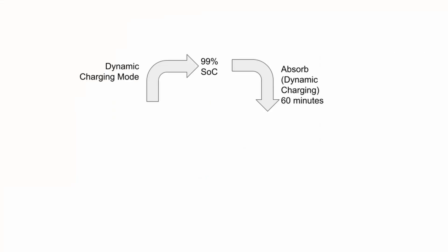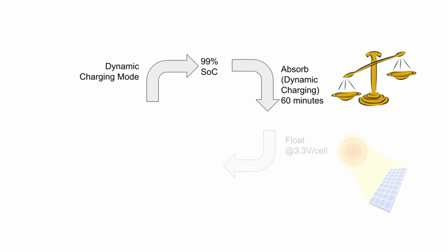This mode continues for a number of minutes, which is configurable by you and it defaults to one hour. During this phase, the dynamic charging continues and it's likely at this time the cell balancing will occur and the battery continues to charge up to 100%. After the timer interval is up, float mode is enabled.